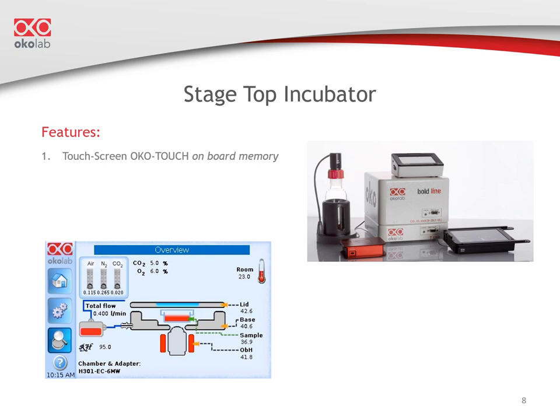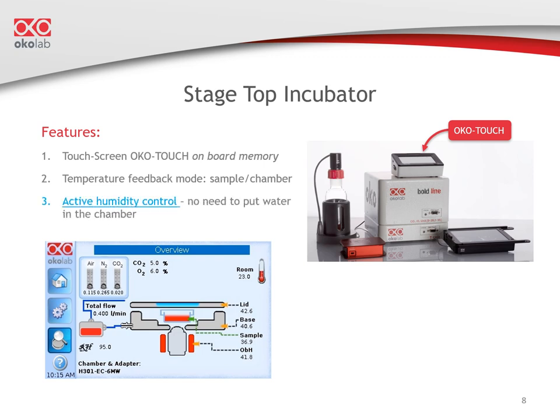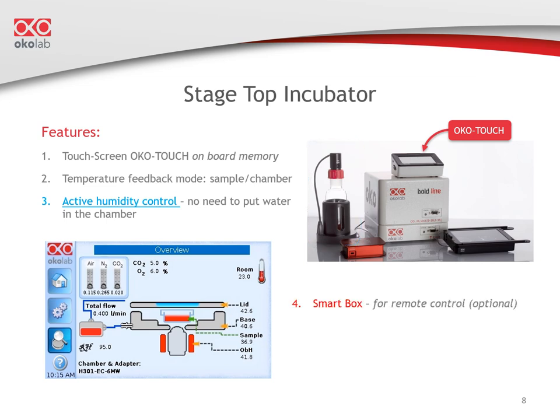OkoTouch is an intuitive touchscreen interface with onboard memory to log data. Temperature can be controlled using sample or chamber feedback mode. Humidity control is active — the humidity module, located away from the stage to avoid accidental spills, is equipped with a humidity sensor, so there's no need to add water into the chamber. The system is compatible with the SmartBox, an optional device for remote data logging and control, and manual gas mixers are also compatible.